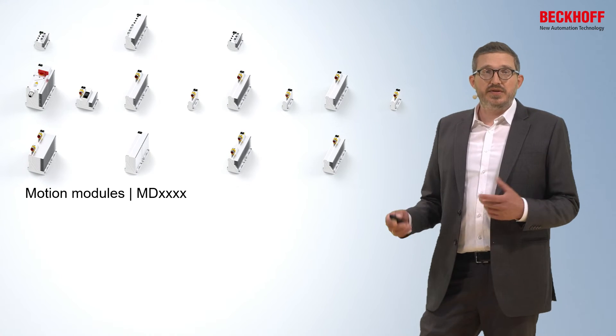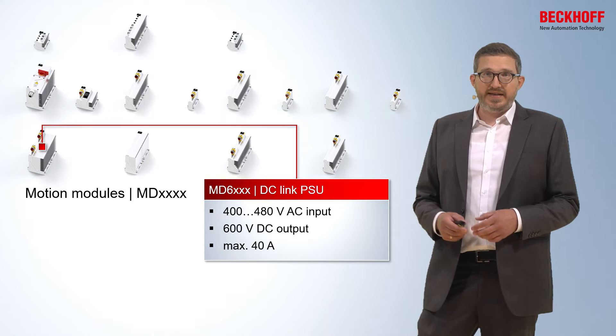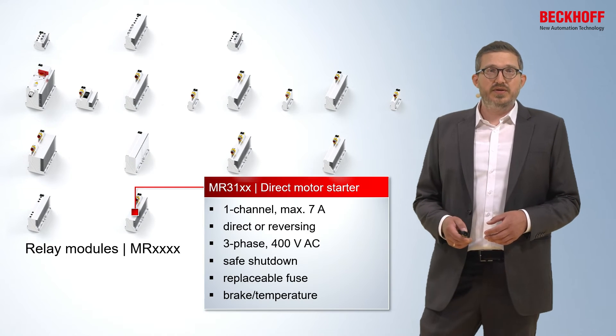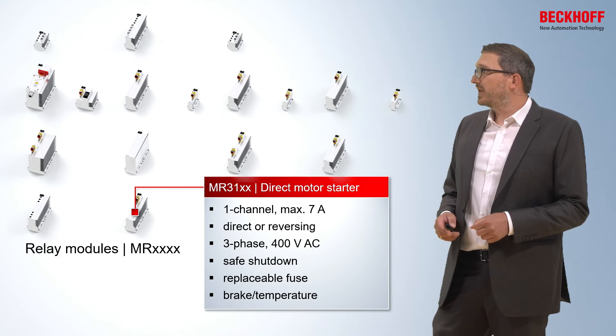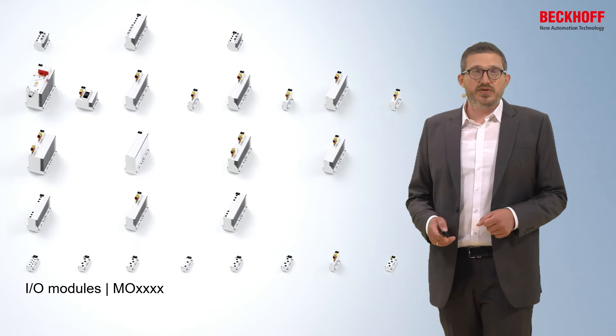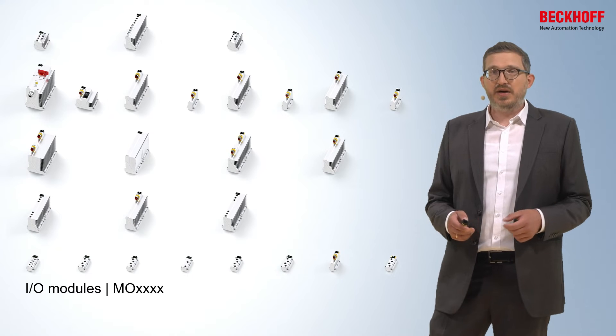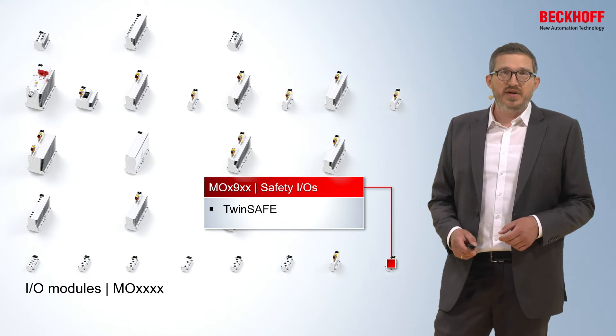If you have motors to control, you can use the motion modules, where you find a dedicated DC link power supply which converts 400 volt AC into a DC link voltage of 600 volt DC. There are also relay modules for switching applications, or you can use the direct motor starter — a one-channel direct motor starter with up to 7 amps output, featuring safe shutdown and integrated connections for brake and temperature sensors. By far the largest category is the I/O modules, covering all terminals known from Beckhoff: digital inputs, digital outputs, analog in and outputs, 48 volt servo drives, and appropriate safety alternatives for any safety application.